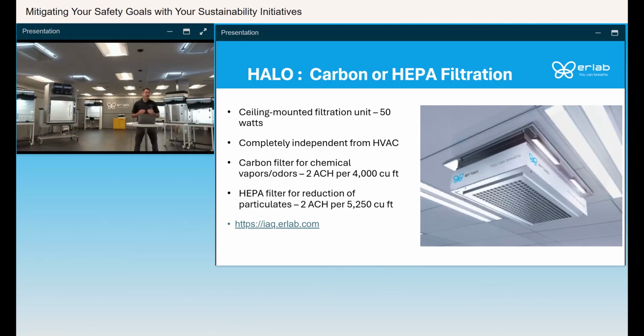It was designed to add air changes into lab spaces that don't have enough ventilation. So you can either have a carbon filter, which is for chemical vapors and fumes. Each Halo with a carbon filter holds about 130 CFM. So our recommendation is to add enough Halos to add 2 air changes per hour, which comes out to about 4,000 cubic feet of space. So if you have a 400 square foot lab with 10-foot ceilings, you need 1 unit. If you had an 800 square foot lab with 10-foot ceilings, you need 2 units.